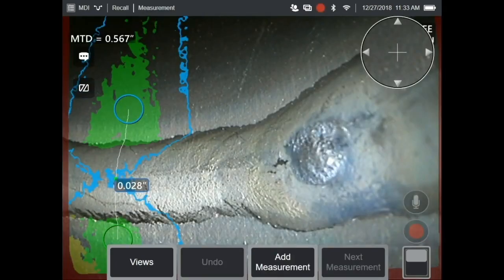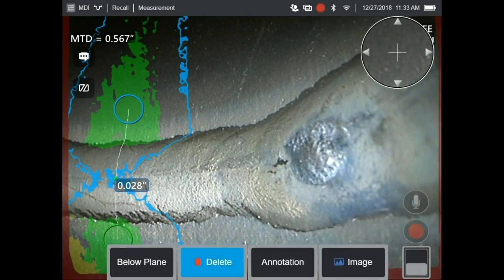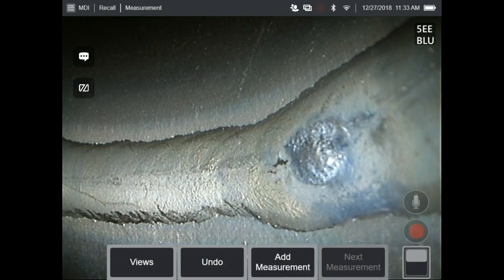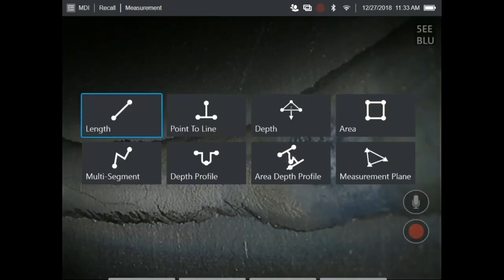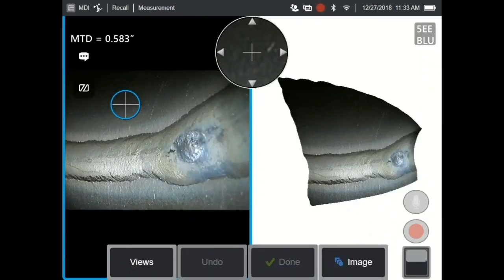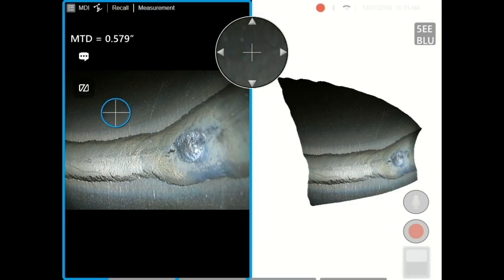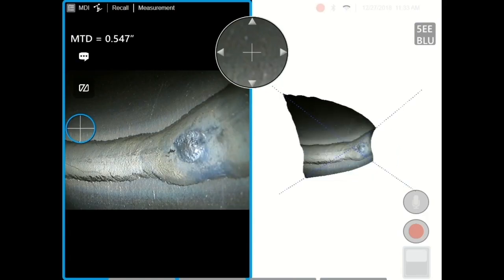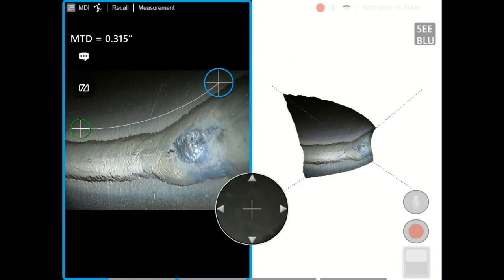I'll hide those keys so that we have a full screen view. Put one cursor on one side of the weld and one cursor across the weld, both on the same side on the tube floor. And the white line between those is following that tube floor in 3D space, calculating that curvature. When I touch below the weld on the other side, you'll see that there's a white line horizontally across the bottom. It is actually mimicking the line across the top, and it's picked the highest point of 41 thousandths of an inch on that strike point.